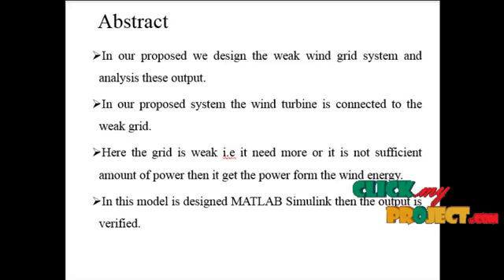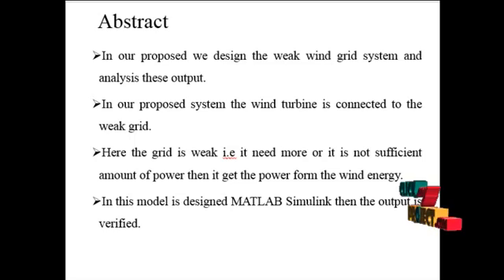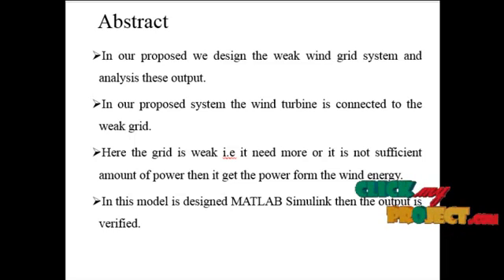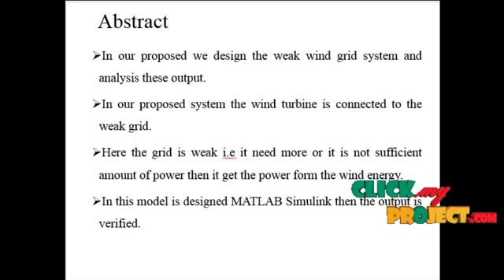A customized internal control scheme of the UPQC device was developed to regulate the voltage at the wind farm terminals and to mitigate voltage fluctuations at the grid side. The internal control strategy is based on the management of active and reactive power in the series and shunt converters of the UPQC, and the exchange of power between converters through the UPQC DC link. This approach increases the compensation capability of the UPQC compared to other custom strategies that use reactive power only. This process is done in the MATLAB Simulink environment.